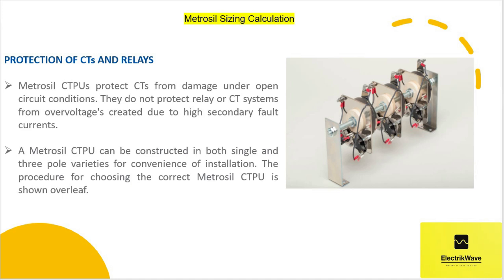Next. Protection of CTs and relays. Metrosil CTPUs protect CTs from damage under open circuit conditions. They do not protect relay or CT systems from overvoltages created due to high secondary fault currents. A Metrosil CTPU can be constructed in both single and three-pole varieties for convenience of installation. The procedure for choosing the correct Metrosil CTPU is shown over leaf.